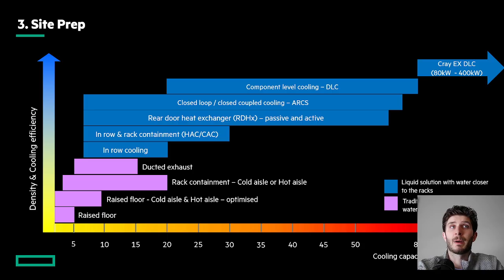The next point is, of course, cooling capacity. If you can power that rack, you also need to be able to cool it. In purple, you see traditional approaches on this chart for cooling with water at the perimeter of the data center. In blue, we see liquid cooling introduced where water is closer to the racks, ranging from hot aisle containment, cool aisle containment, rear door heat exchangers, to a closed loop cooling solution we call ARCs for full containment, and DLC for direct to chip liquid cooling. The x-axis shows cooling capacity per rack growing over time, and the y-axis shows a rough density and cooling efficiency metric: the more liquid cooling you use, the more efficiently you'll cool these systems, and the better your total cost of ownership will be.